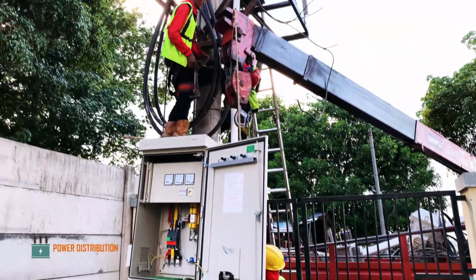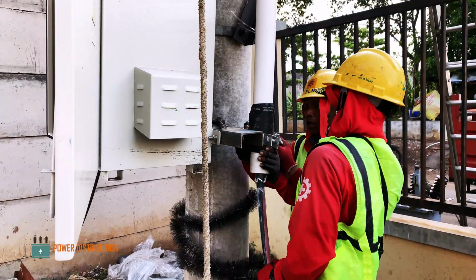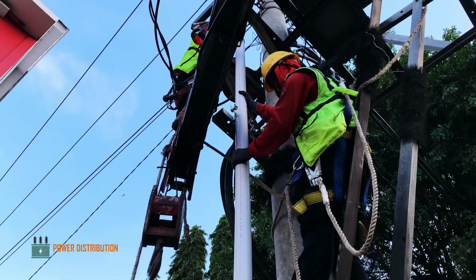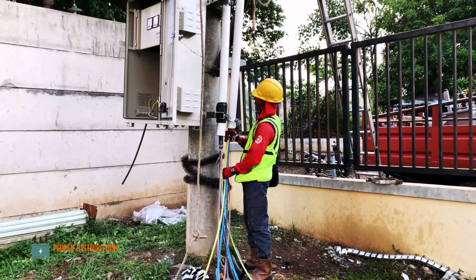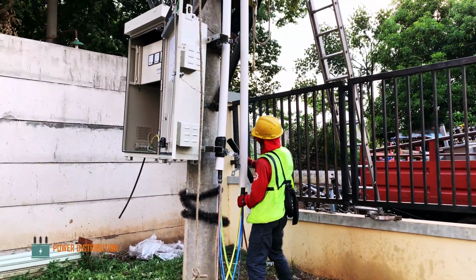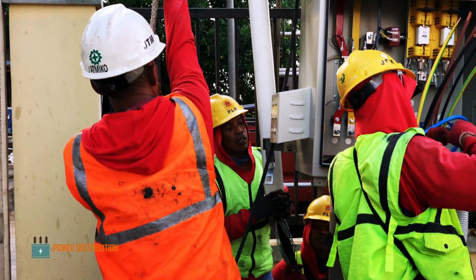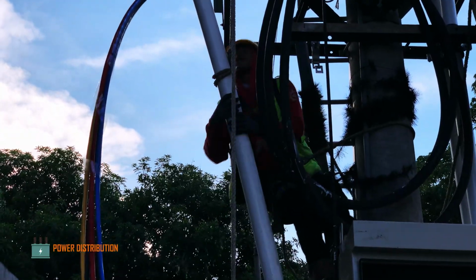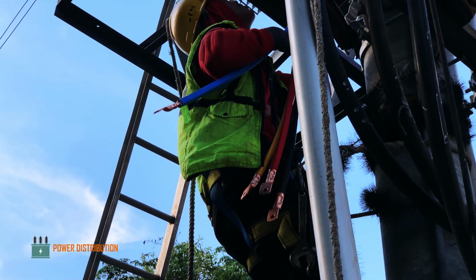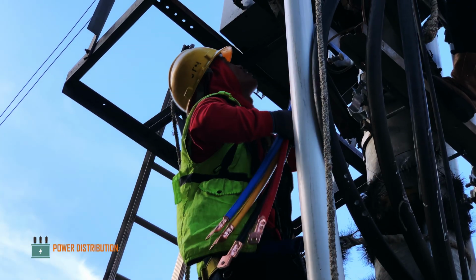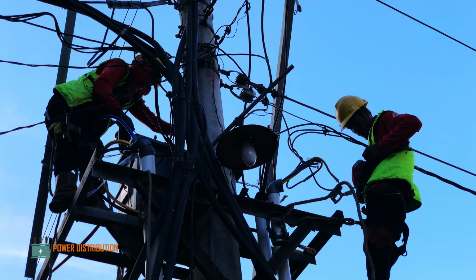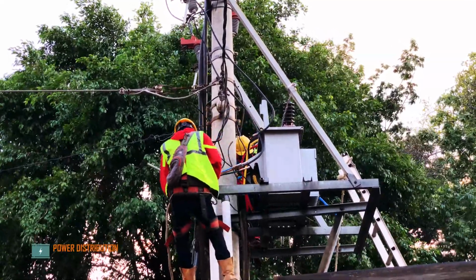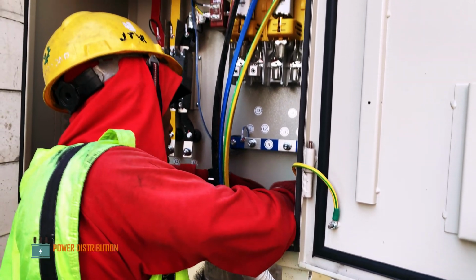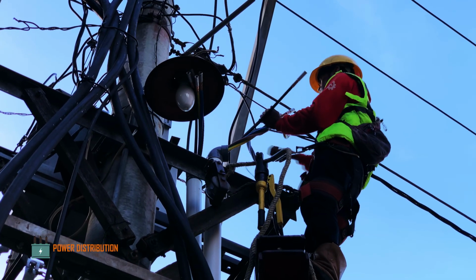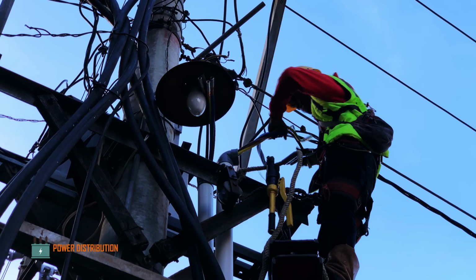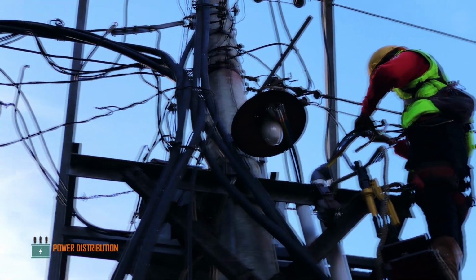After the box firmly attached, the crews begin to install all the main and secondary cables and secure it onto the cross arm using 3.5 inches ball band. Attaching the main power cables, and then ready to be connected to the bushing of the transformer. Then the crew adds some plastic spiral to add additional protection. Meanwhile, the lineman is aligning the phase mark to the existing wires, and then to be connected to the aluminium distribution wire.